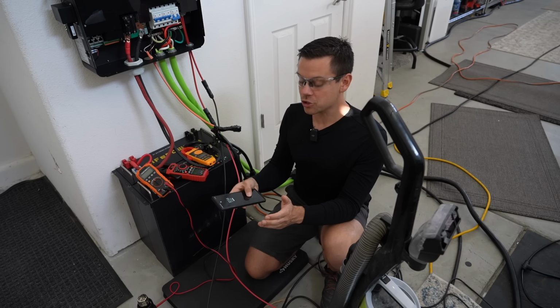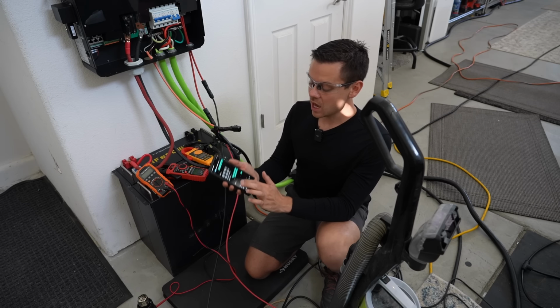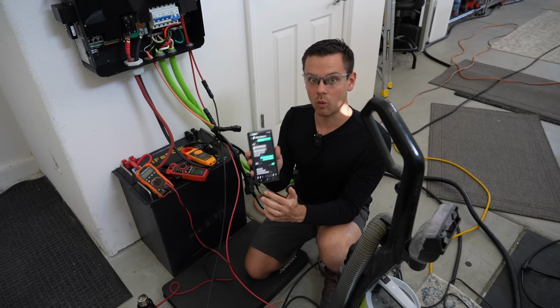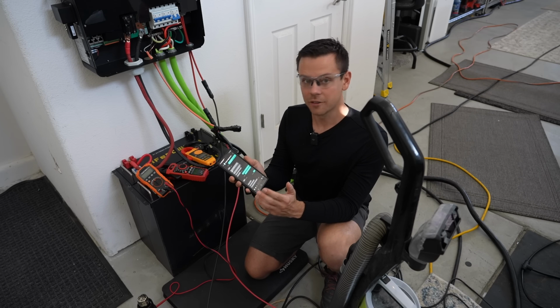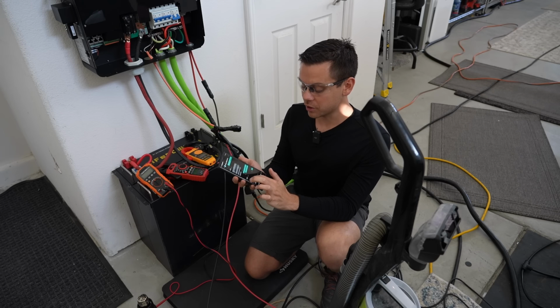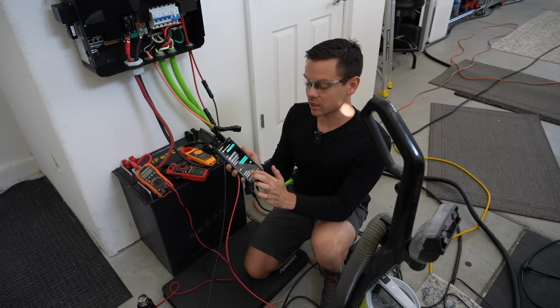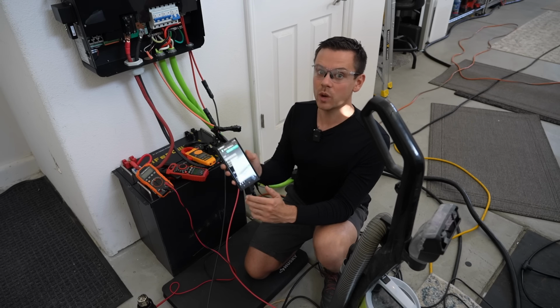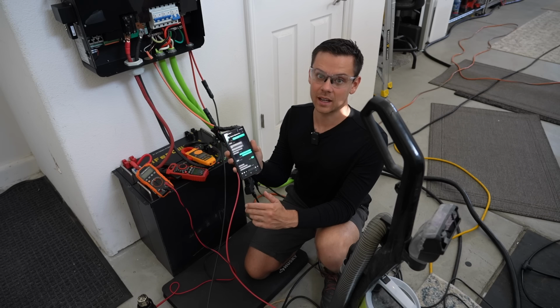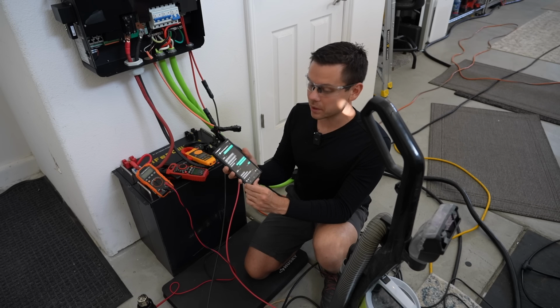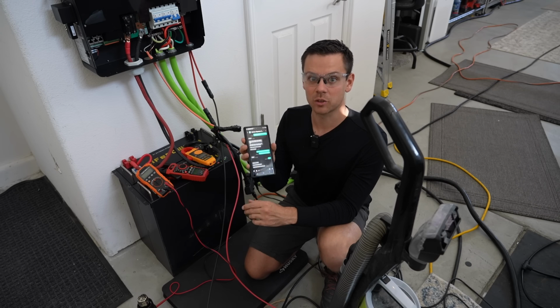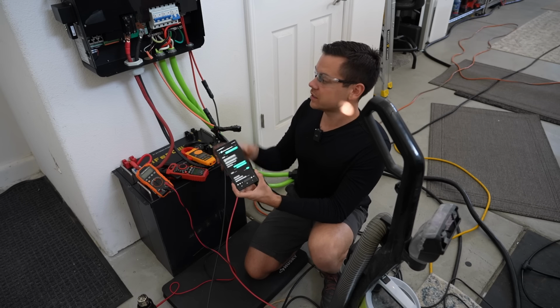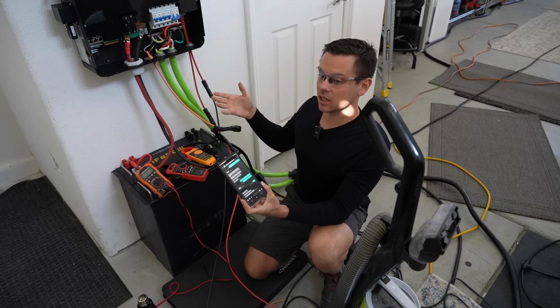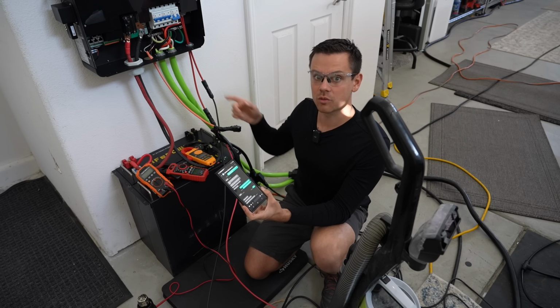When it comes to 120 volt loads, single phase, the maximum is 3,000 watts. There's no surge rating for a single leg. Also, they said in the test report the max that they could get was 28 amps, and we loaded this thing down with 48 amps. So it did really good, but I would not depend on this if you have to run large inductive loads on a single leg. If you have large inductive loads on 240 volts, this should run it just fine.